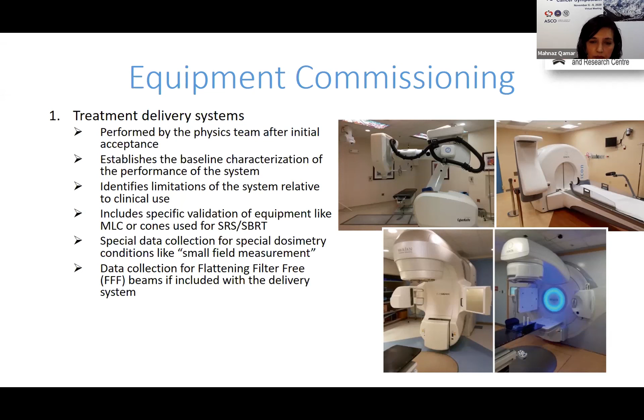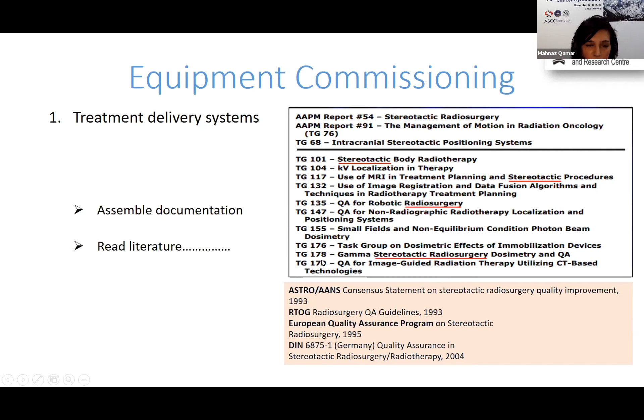It includes the specific validation of equipment like MLCs or micro MLCs or cones used for SRS SBRT, special data collection for dosimetry conditions like very small field sizes, which is often referred to as small field dosimetry, and data collection for the flattening filter-free beam, which a lot of these machines have. So having an understanding of what those are, and being able to commission them for the system. Before we get into that, there is a lot of documentation available for the physicists to go through. They should go through that and have a good understanding of what is needed and what they can foresee. And there's a lot of literature available, so refer to that.